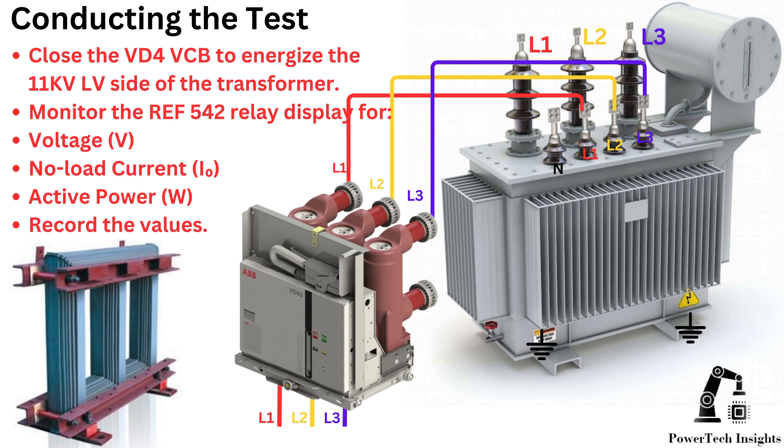Conducting the test: close the VD4 VCB to energize the 11 kV LV side of the transformer. Monitor the REF 542 relay display for voltage, no-load current, and active power. Record the values.